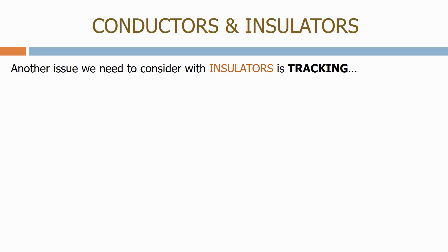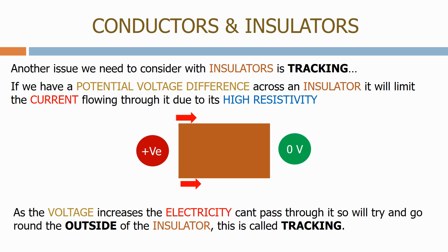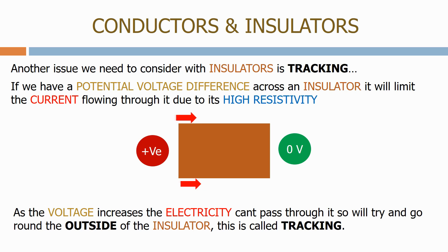Another issue we need to consider with insulators is tracking. If we have a potential voltage difference across an insulator, it will limit the current flowing through it due to its high resistivity. As the voltage increases, the electricity can't pass through it, so it will try to go round the outside of the insulator. This is called tracking.